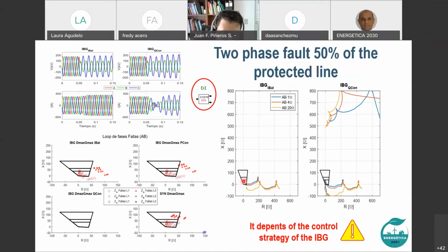Okay, it's working properly. But when we are using the reactive strategy control, the problem is the impedance goes so far away from the detection capability of the relay. Here is the balance mode of the current. Here is the reactive constant mode. Then we are not able to see it.